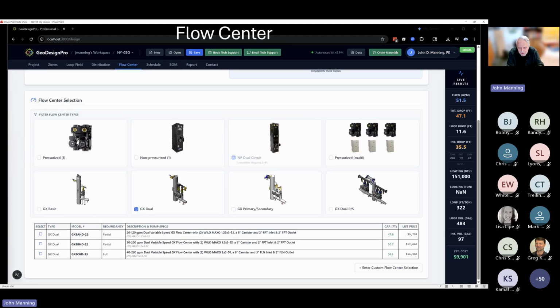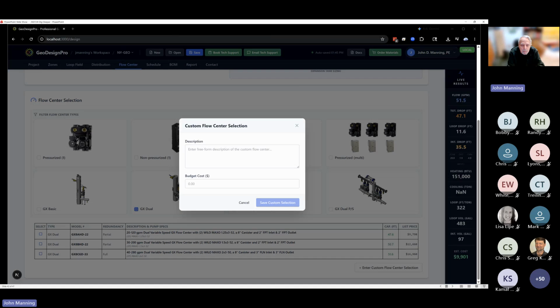From a flow center selection, we have a variety of readily available flow centers. These are typically maybe for 120-ton systems or less. And the program will identify in the lower table those that meet the requirements, and it'll indicate whether it provides partial redundancy or full redundancy. But if you don't want to use any of these flow centers, there's an option down here on the lower right that if you click on that, it brings up a window that you can describe the pumping system you do want to incorporate into your system. And you can enter a budget cost to help keep track of the estimating function of our software.